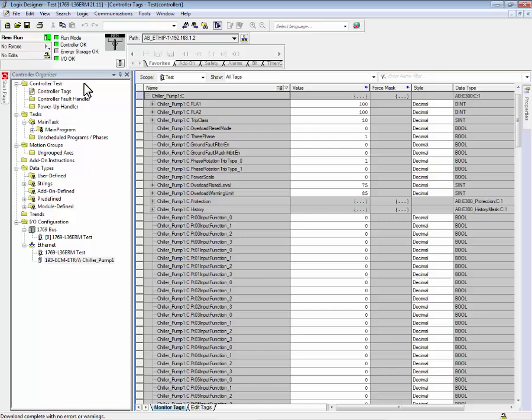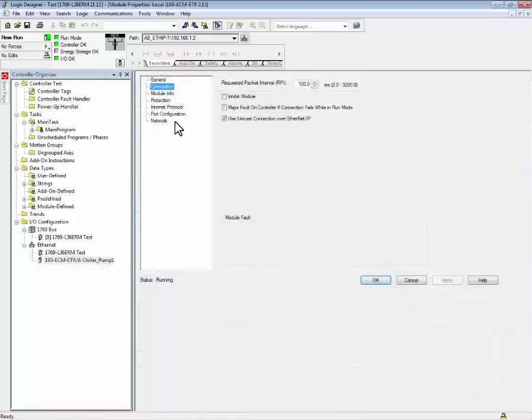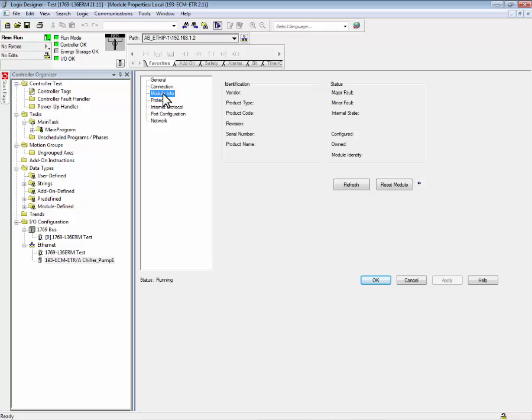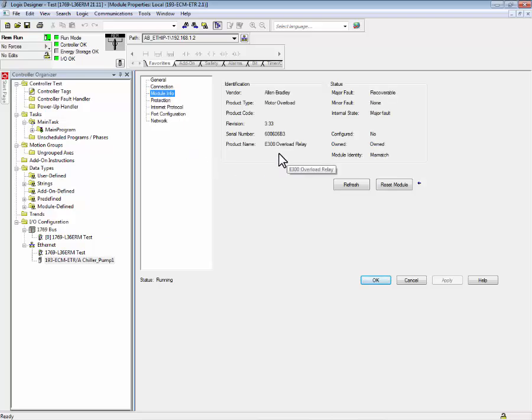Another way to view this is by going into the device profile and select module information. And we can verify that our E300 electronic overload relay is communicating with our Logix controller. The status indicator shows that our device is running.